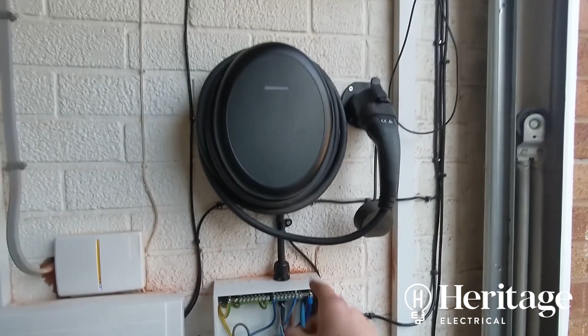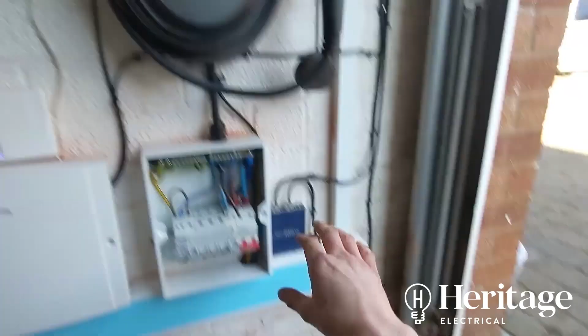Right, so just temporarily linked it out with the earth bar to do our R1, R2 measurement. Took the cover off. Obviously it's negligible, some meters coming back as 0 because it's a tiny run of quite chunky cable between there and there. So 0.01 essentially. So if we go 0.34 add 0.01, that gives us the ZS of 0.35, which is well within what it needs to be. You can see there 0.68. So if there is a fault current on there, it's going to trip the breaker in easily enough time to meet our disconnection times.